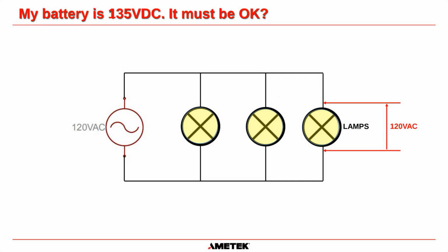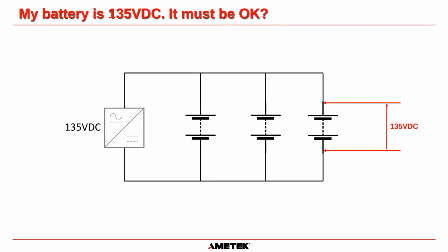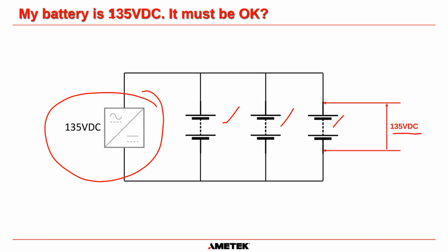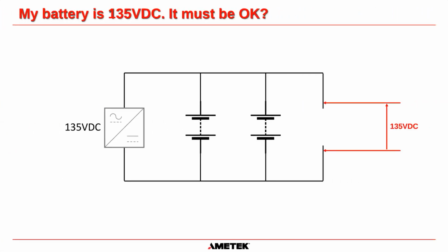Hopefully that makes sense. Basic light circuit. If we removed one lamp, let's say it's a screw bulb, we remove the bulb. If we still go on the fitting and measure at the terminals, we will still get 120 volts, even though there is no bulb there anymore. We still have 120 volts AC there. And the same applies to DC. If we have a 135 volt charger here, and we have 3 batteries in parallel, we are going to measure 135 volts DC across the positive and negative terminals of this battery. If we remove this battery completely, but we still measure at the terminals of the cables going to that battery, we will still measure 135 volts DC, even though there is no battery there.